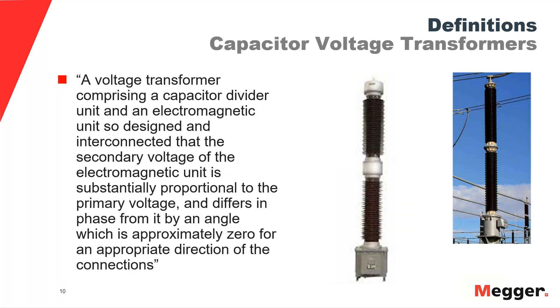The current transformer: the secondary current under normal conditions of use will be substantially proportional to the primary current, with the difference in phase by an angle which is approximately zero for the appropriate direction and the proper connection. Similarly, in the case of the voltage transformer, the secondary voltage in normal conditions of use is substantially proportional to that primary voltage, and that secondary voltage will differ in phase from the primary by an angle that is approximately zero when connections are appropriate.